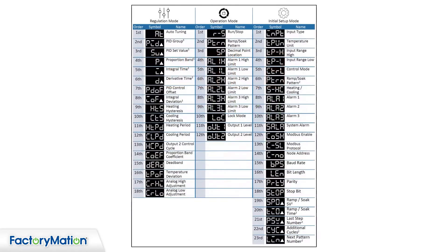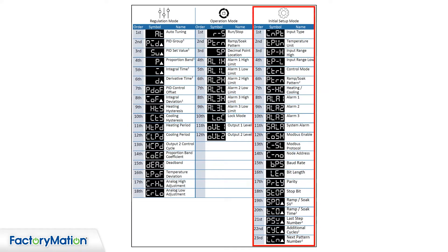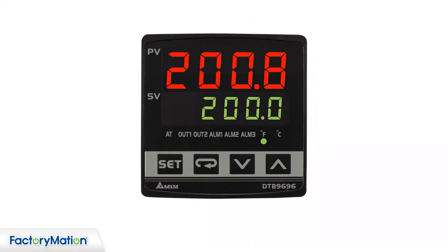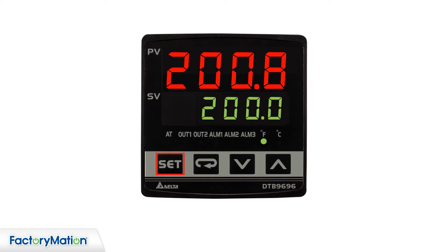The DTB controller is configured with the initial settings mode. This mode sets parameters like sensor input, temperature units, control modes, and RS-485 communications. To enter the initial settings mode from the operation mode, press and hold the Set button for three seconds.